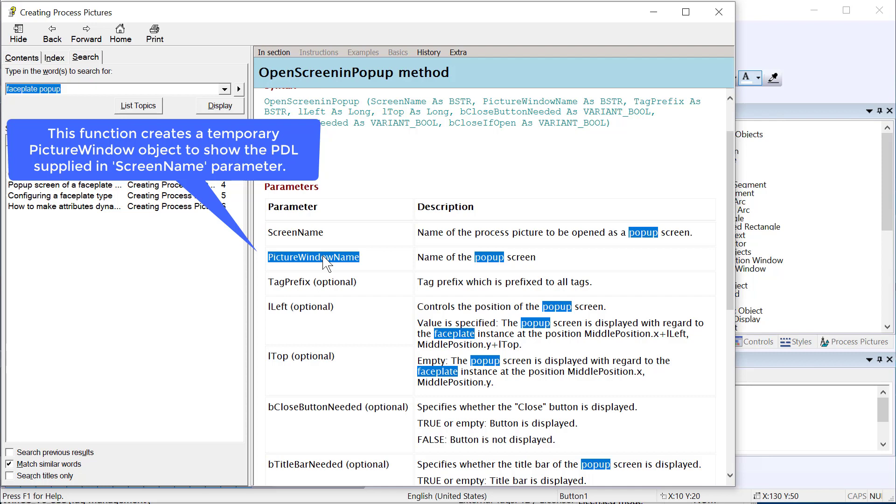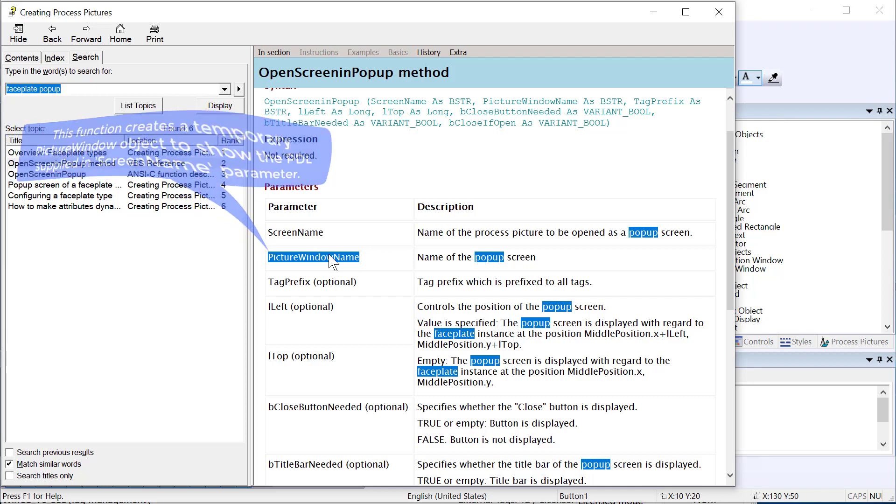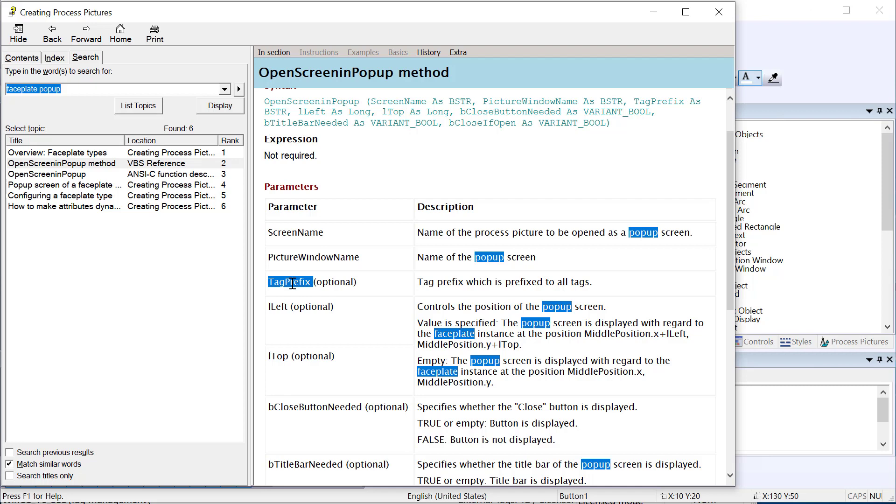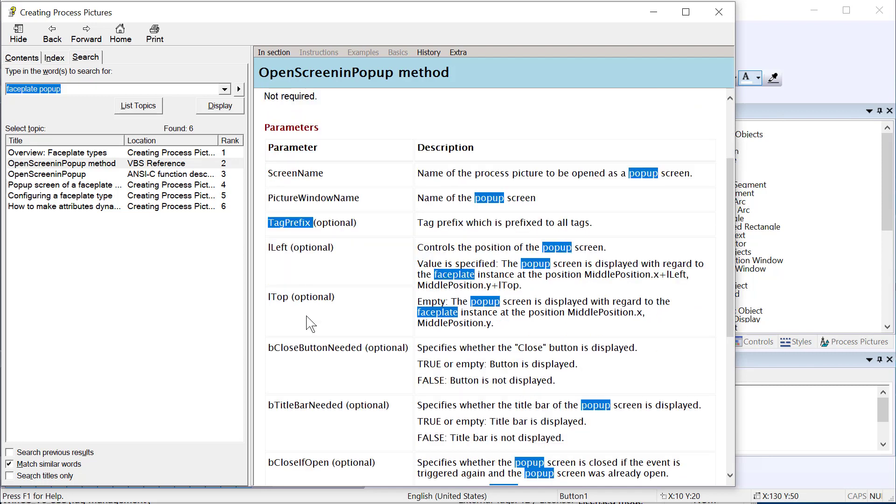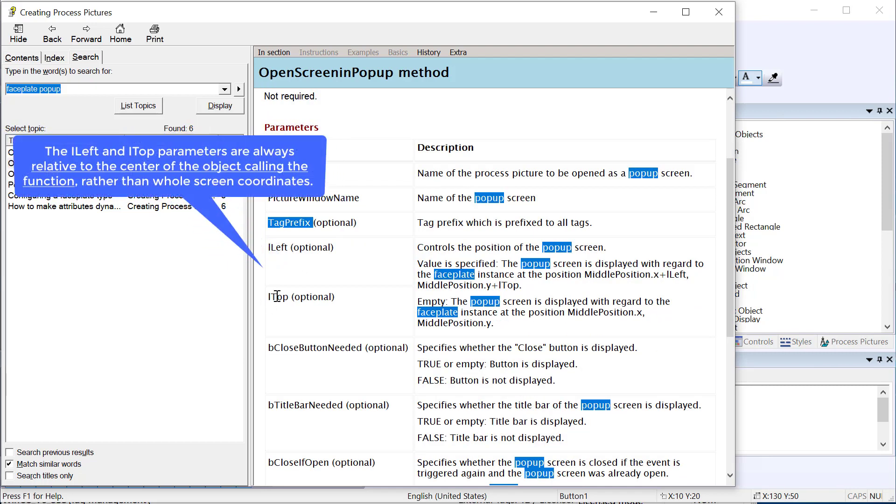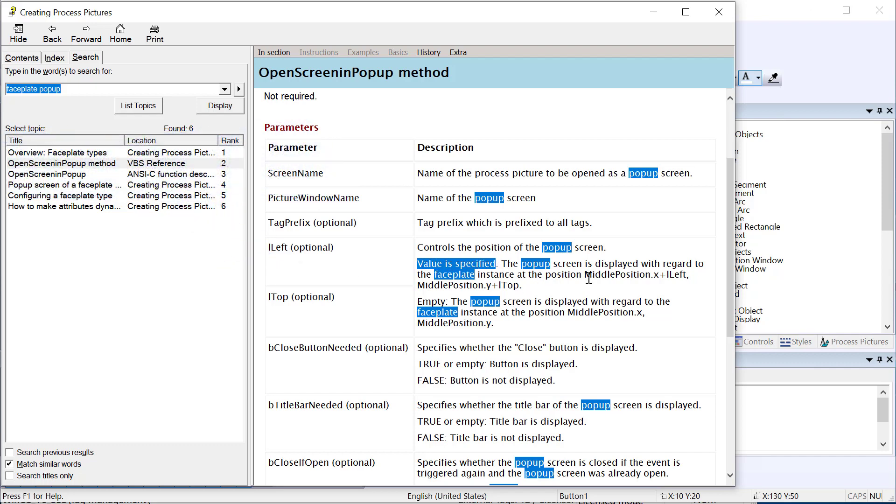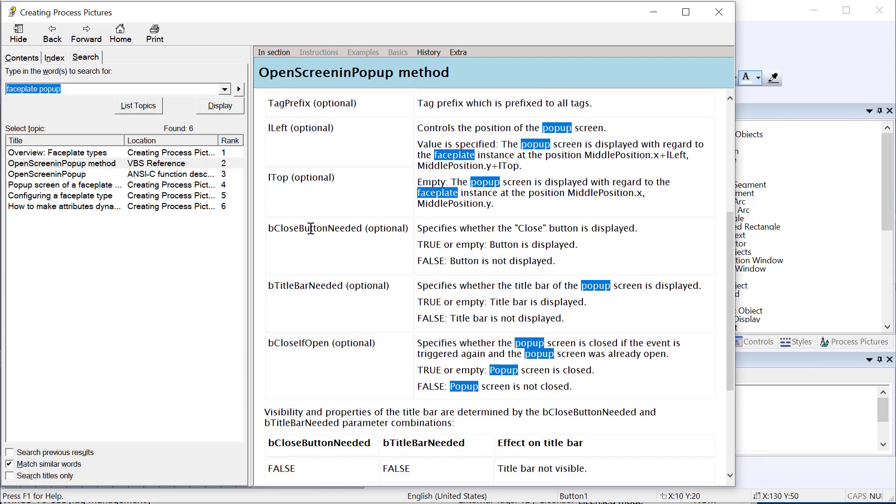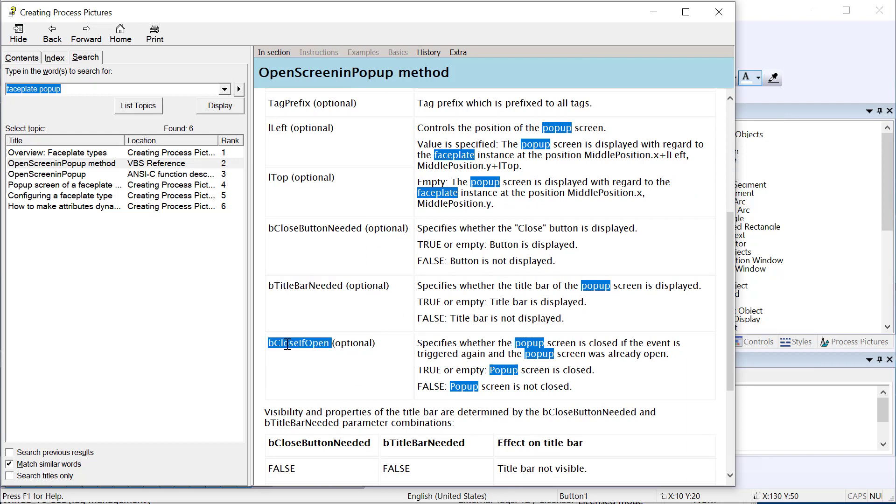That's going to be our pop-up PDL. You also have to give the picture window a name. You're not going to use a picture window object, but when you call this function, it creates a picture window on the fly. So you have to give it a unique name. If you are using tag prefix, you're going to give it that tag prefix or you can leave it blank. We've got the left and top. So you can define where this pop-up pops up with relation of the object that called it rather than just any coordinates on the screen. If you specify a value for these two, then it is going to basically calculate whatever value you put in there away from the middle of this. If you just want the corner to pop up in the middle of the object, then you leave it empty. You can see that it says the position, middle position dot X, middle position dot Y. That means the corner of this pop-up is going to show up near the middle of that object.